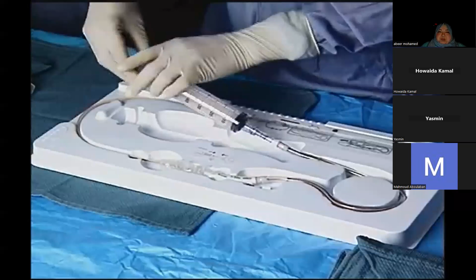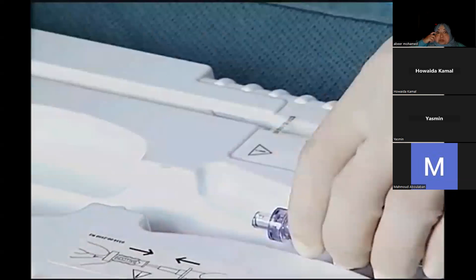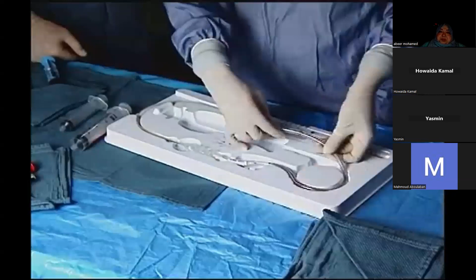Aspirate 30 cc of air with the enclosed 60 cc syringe. This maneuver will compact the balloon membrane, allowing for easy removal from the tray and smooth insertion. Disconnect the syringe from the one-way valve, leaving the valve in place on the balloon catheter. Now, remove the balloon from its protective tray by lifting the Y fitting and catheter from the tray.